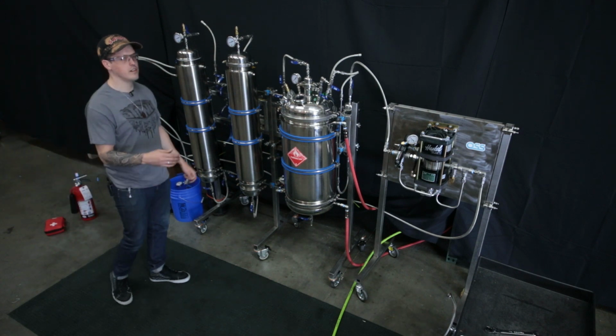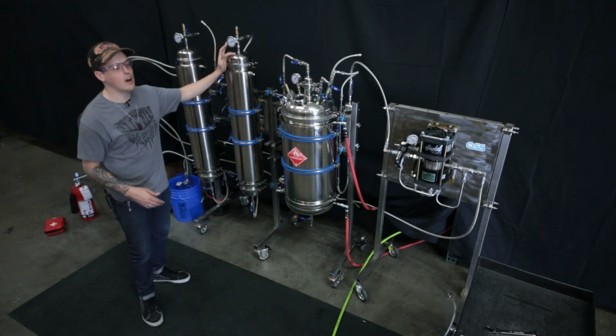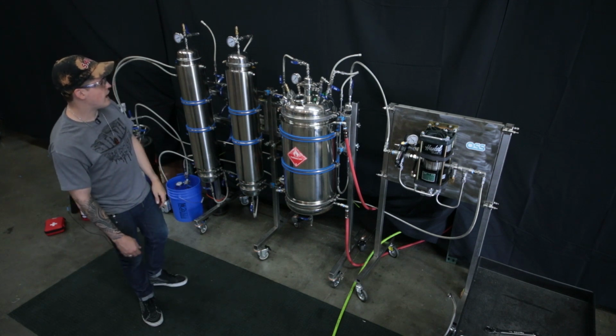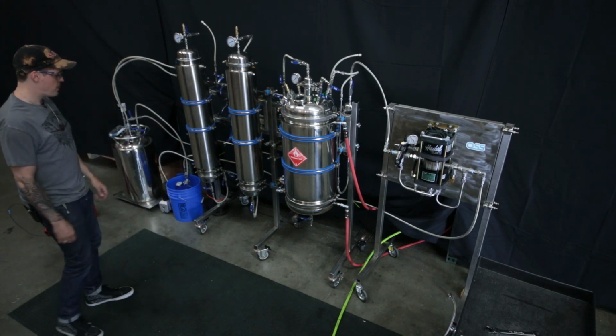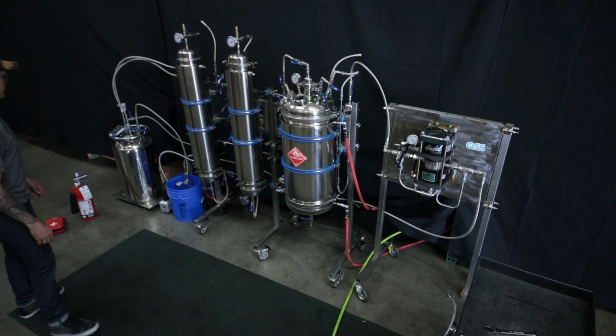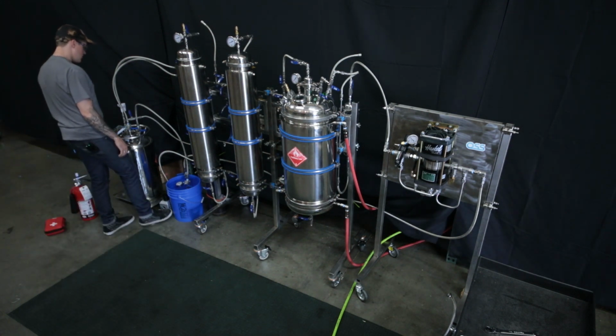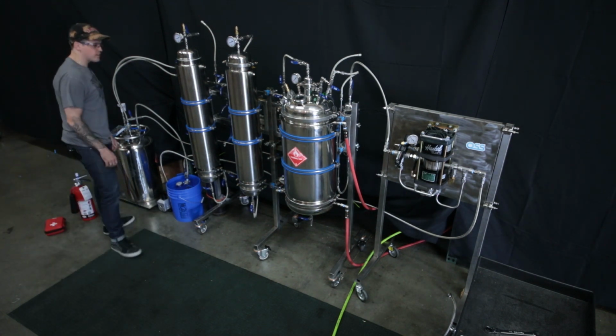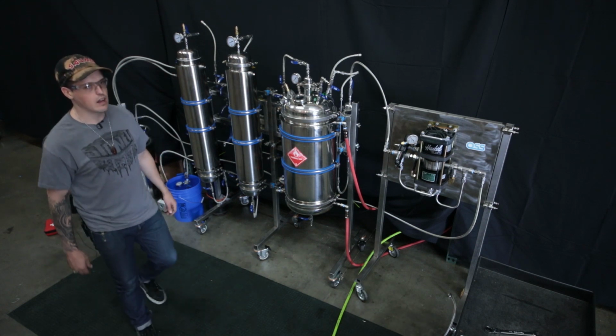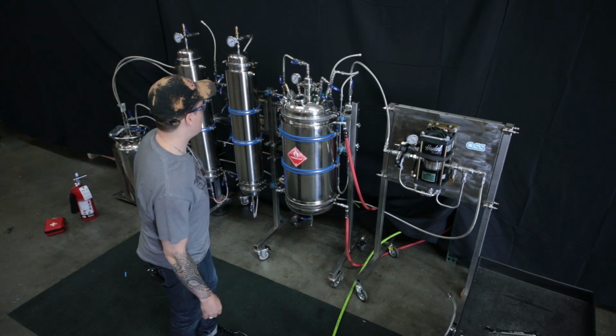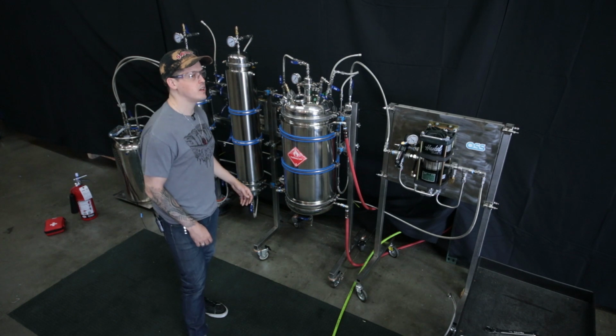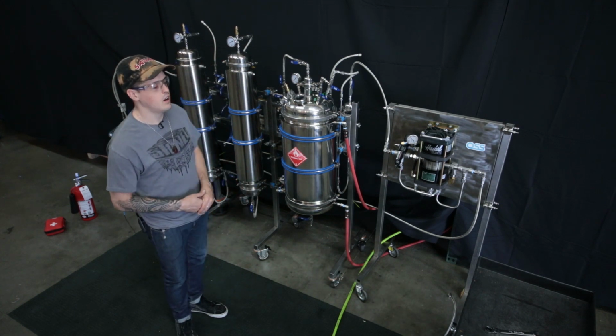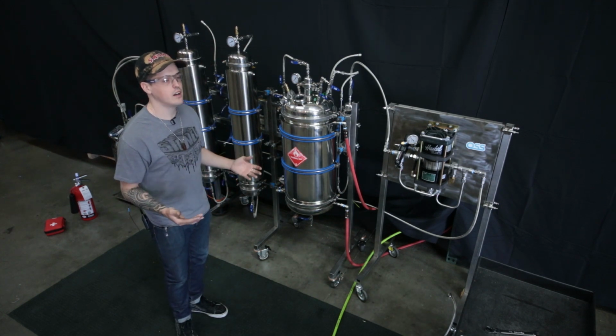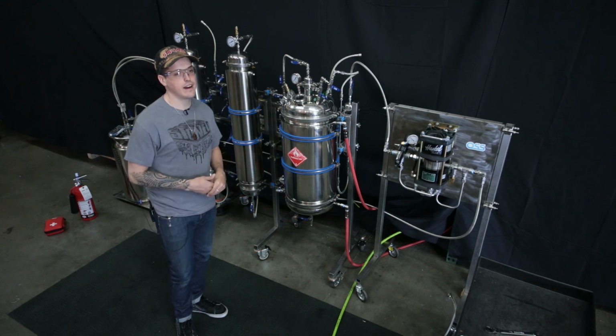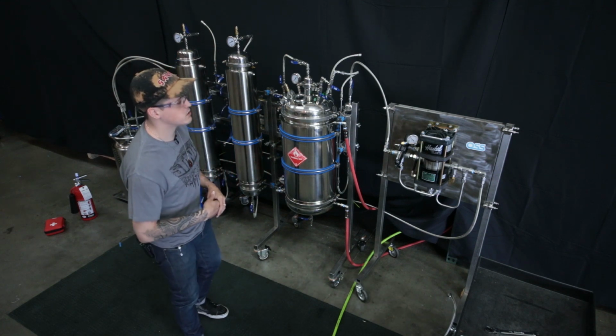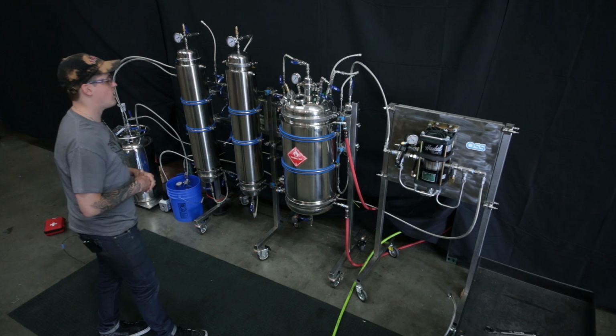Looks like the needles on the gauges are slowly moving down, so I know that we're pulling a vacuum slowly but surely here. This is going to take about 3 minutes or so. Depends on the vacuum pump, the size of CFM, the displacement that it has, how long this process is going to take. But once we reach a full vacuum, which is 30 inches of mercury, you're going to want to leave your vacuum pump running for an extra couple minutes to make sure to pull out any of the last molecules of oxygen out of there.